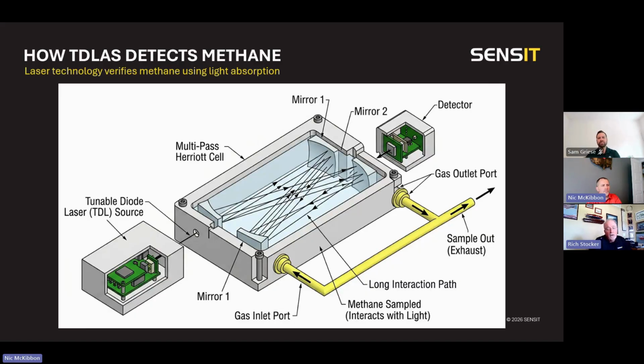And this is really the nuts and bolts of the heart of the PMD2. Instead of just throwing that light out and utilizing any reflective source we find out in the field with the LZ30 and with a variable length of light path, we build a Herriott cell with reflective mirrors, and we have a known volume sample chamber, and we have a known path length of light, which allows us to quantify the readings on this technology. Depending on how long the path length is sets the standard for how low of a resolution the unit will read. The longer the path length, the smaller amount of gas it'll pick up. As we have it configured today, it'll pick up roughly 1/10 to 3/10 of a ppm, all the way up to 100% with the short path on the laser itself.